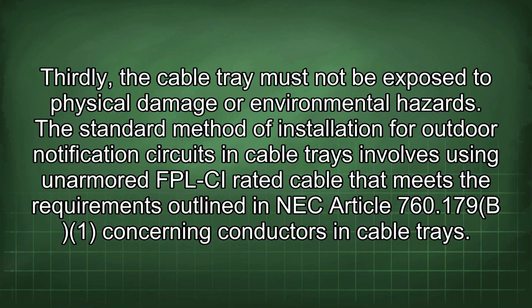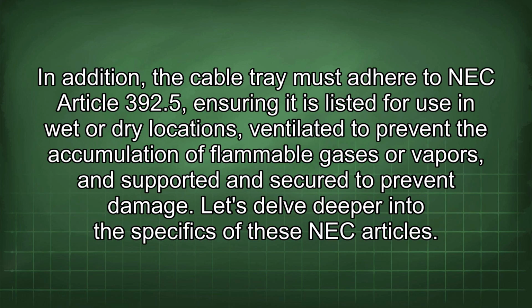The standard method of installation for outdoor notification circuits in cable trays involves using an unarmored FPL-CI rated cable that meets the requirements outlined in NEC Article 760.179 concerning conductors in cable trays. In addition, the cable tray must adhere to NEC Article 392.5, ensuring it is listed for use in wet or dry locations, ventilated to prevent the accumulation of flammable gases or vapors, and supported and secured to prevent damage.